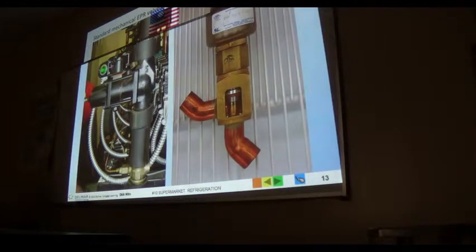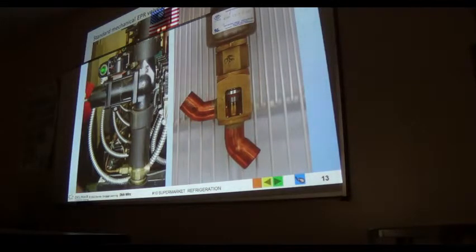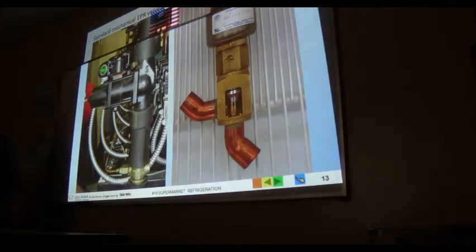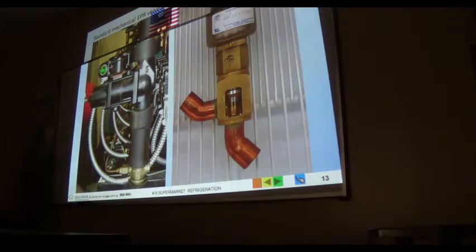Mind you, it can do it, but it's going to take maybe three times as long as a regular system. If you had a bunch of food above box temperature, the food will probably end up spoiling before the box comes down to temperature. So you don't want that. You want the box always pre-chilled or frozen to temperature, and then load it. That's why most supermarkets bring in refrigerated trucks: the food is already cold, so they don't have to experience all this load fluctuation. Keep that in mind, because there will be a couple of questions like that on your final exam.